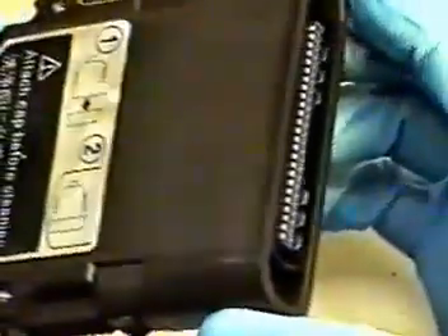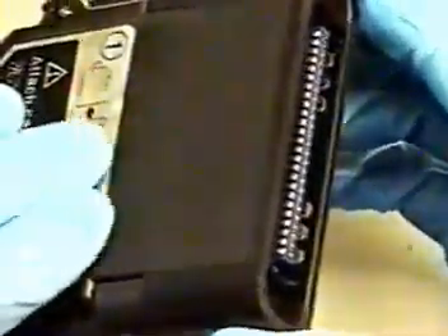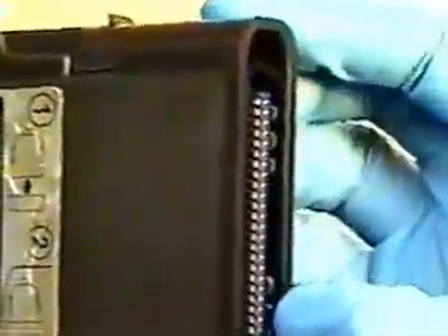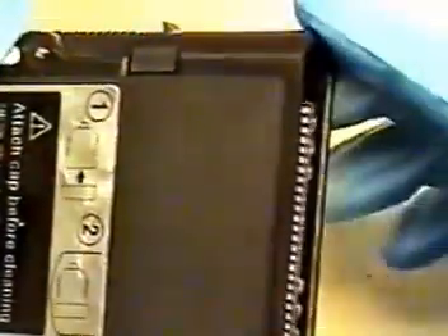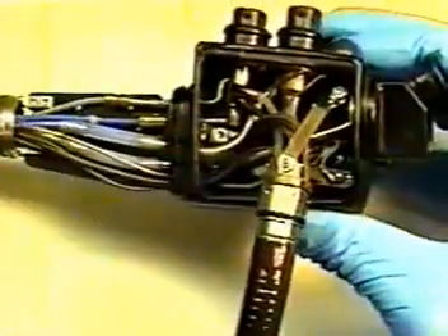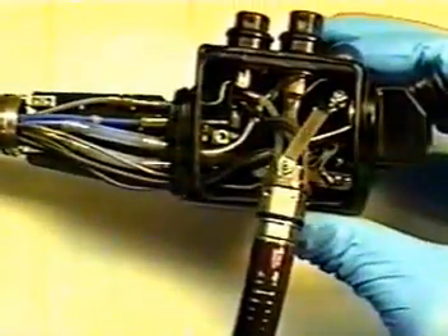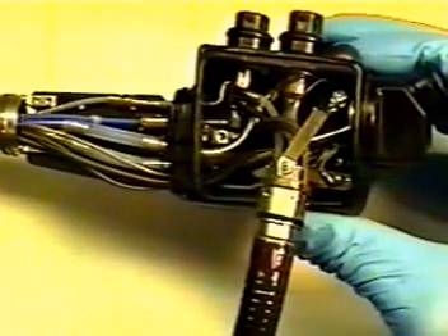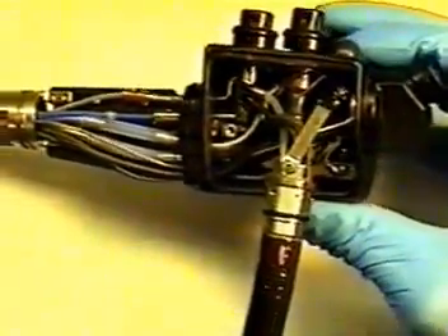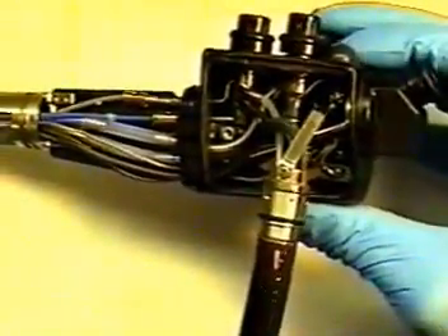Now you can safely test CHA assembly in the EPX 200 processor. If you do not still have an image, you will need to remove it, resolder wires, and test again in processor. Once you have gotten a good image on your EPX 200 processor, we will now need to reseal the entire scope and test for leaks.